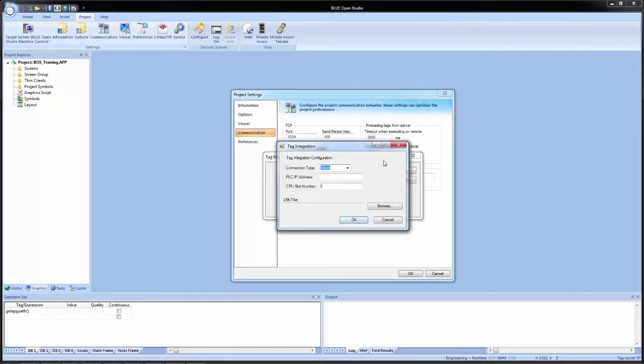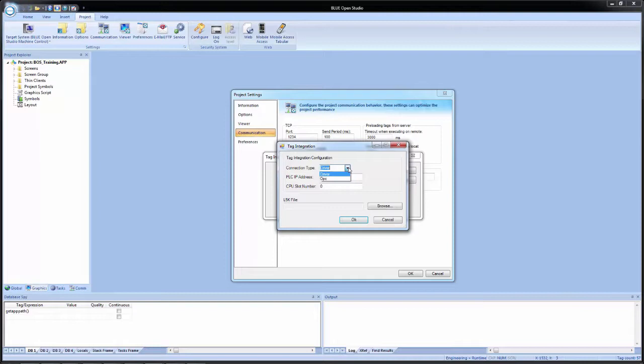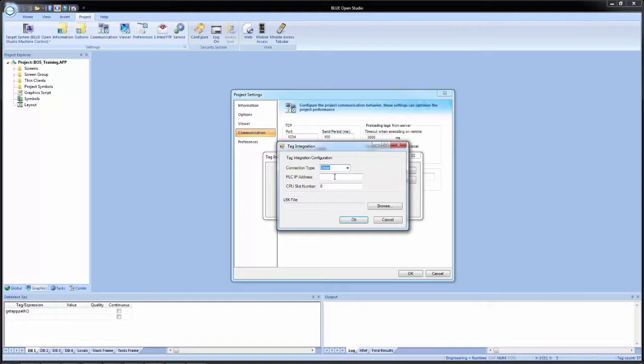Now it comes up with the tag integration settings window. Under connection type, there are two options, driver and OPC. We can select driver. And in this case, what will happen, as I stated earlier, a driver worksheet will be created to communicate to this specific device. If we select OPC, we'll have to create an OPC connection in order to communicate. So we're going to leave the connection type set to driver.